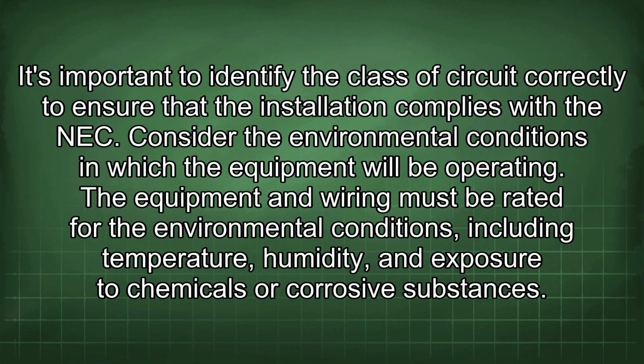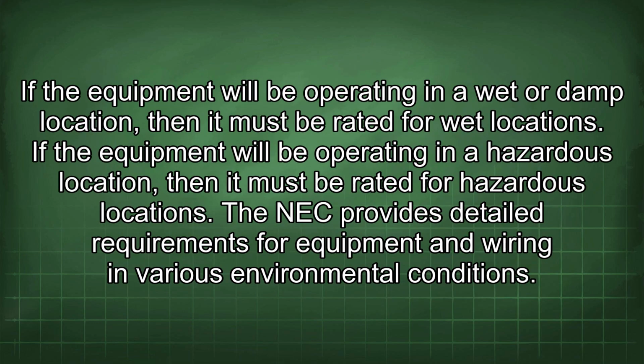Consider the environmental conditions in which the equipment will be operating. The equipment and wiring must be rated for the environmental conditions, including temperature, humidity, and exposure to chemicals or corrosive substances. If the equipment will be operating in a wet or damp location, then it must be rated for wet locations. If the equipment will be operating in a hazardous location, then it must be rated for hazardous locations. The NEC provides detailed requirements for equipment and wiring in various environmental conditions.